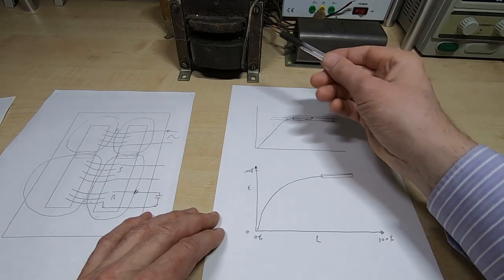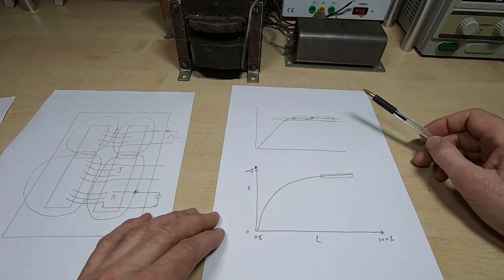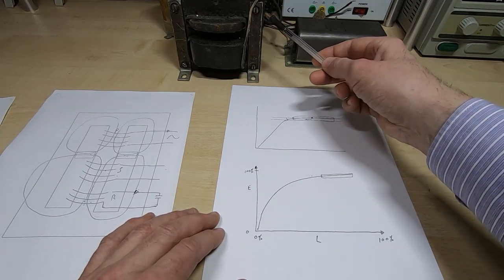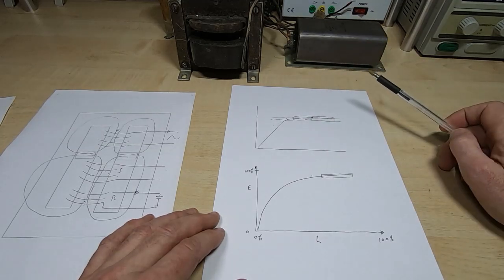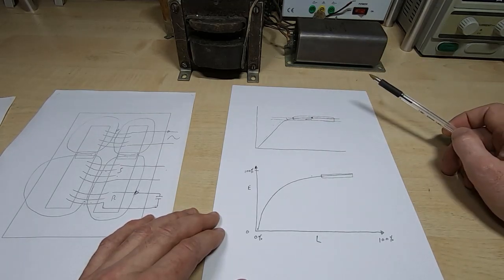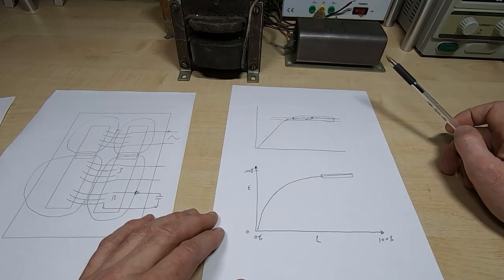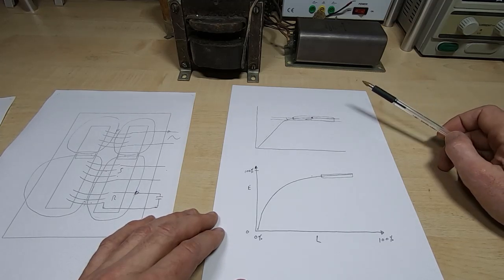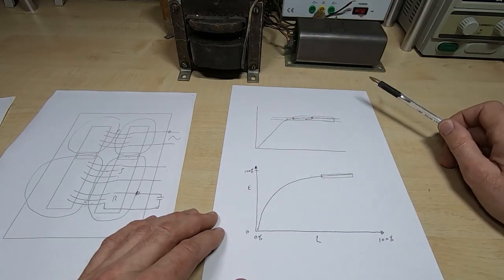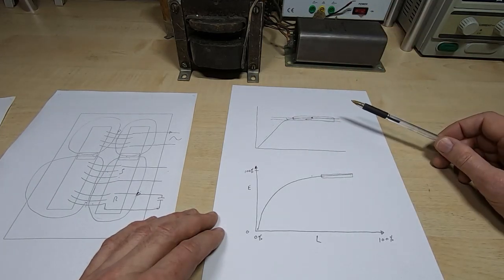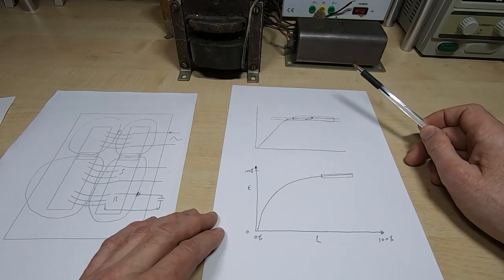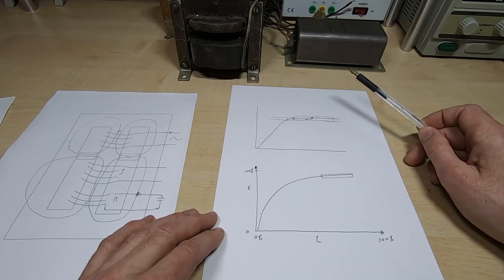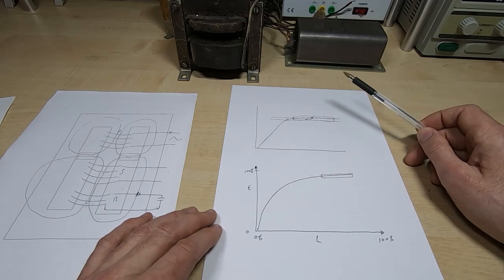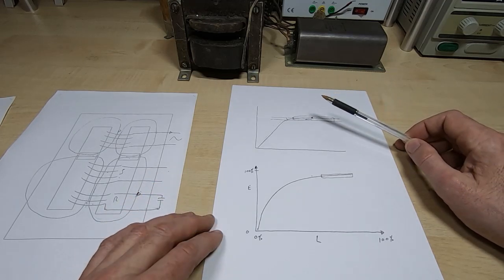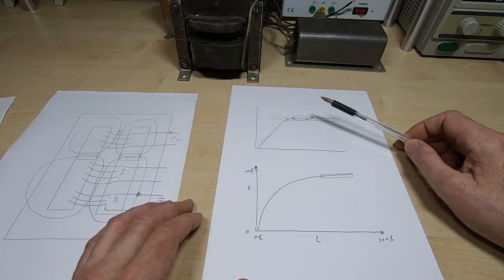One of the other aspects of the way these work is this: if you short circuit the output of a standard type of transformer of this size, you'll probably blow the fuse or do something very bad, and almost certainly the magic smoke will escape. Ferroresonant transformers don't do that. If you short circuit the secondary, it effectively shuts the transformer down and the power flowing through it drops off to a very low value. So it's an inherent safety feature of them. They have some very strong points.